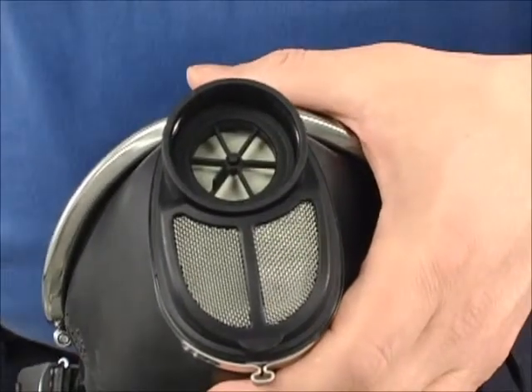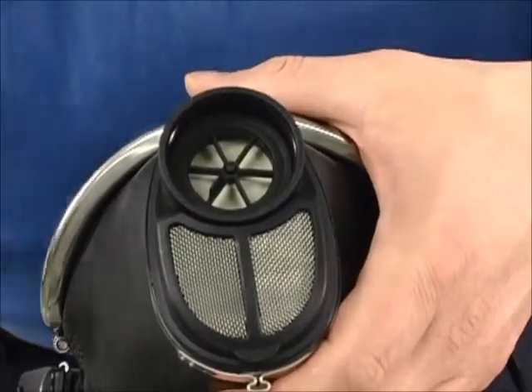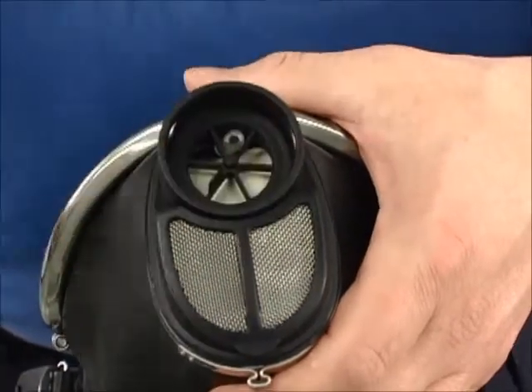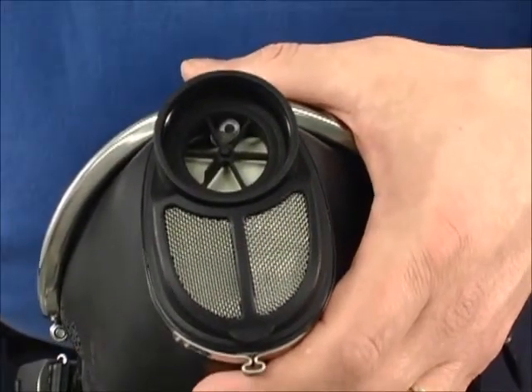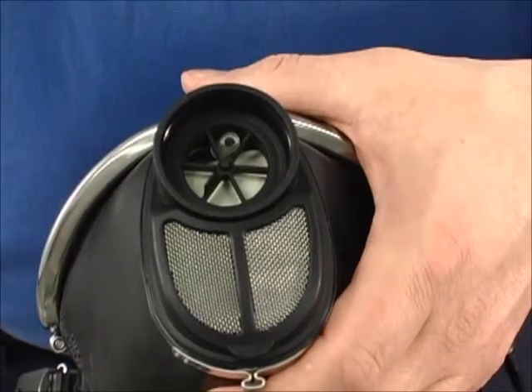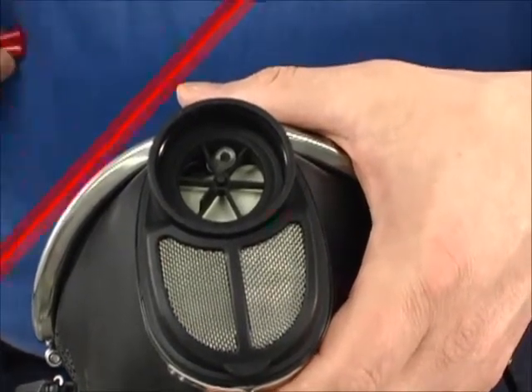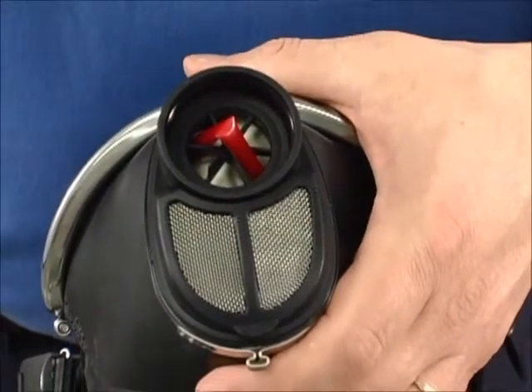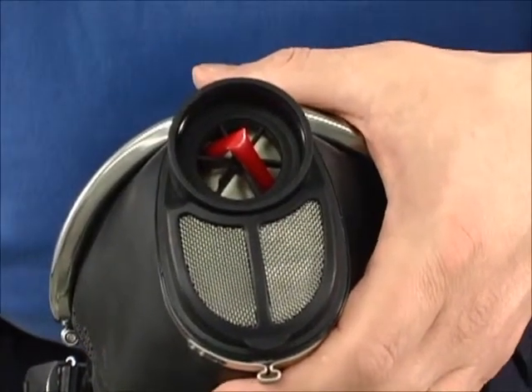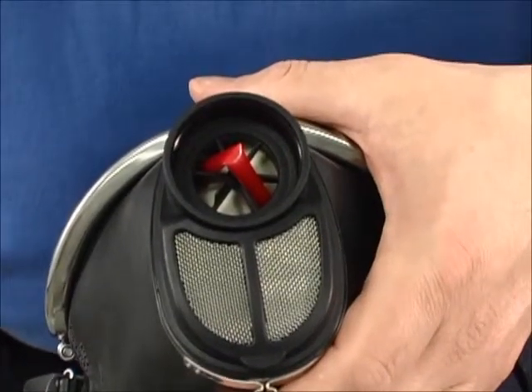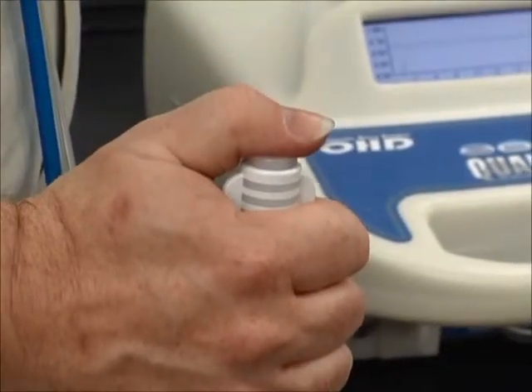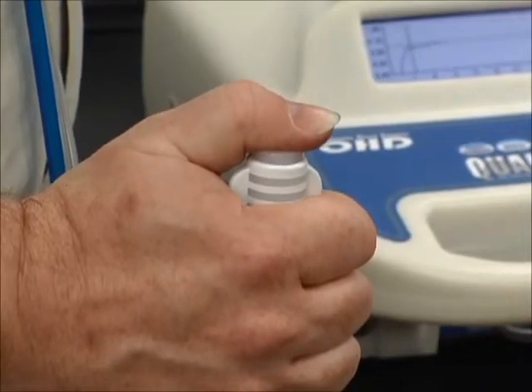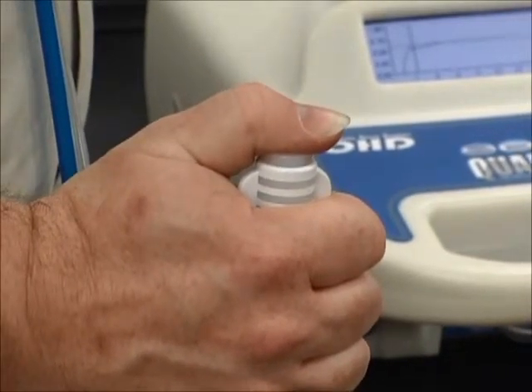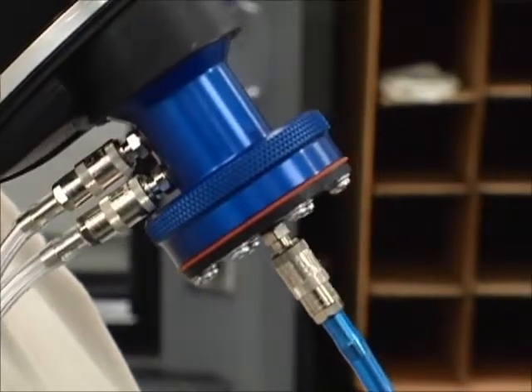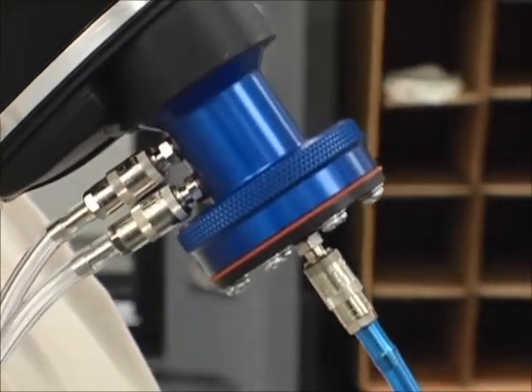Before beginning the test, you must make sure the inhalation valve on the mask is either removed or propped open. You may use tubing, straws, or any material that will keep the inhalation valve open during the test. If this does not occur, the inhalation valve will not allow the Quantifit to exhaust the air out of the mask and measure the proper leak. As the Quantifit tries to remove air from the mask, the inhalation valve will inadvertently create a seal, which would inhibit the Quantifit from removing air and monitoring leak inside the mask.